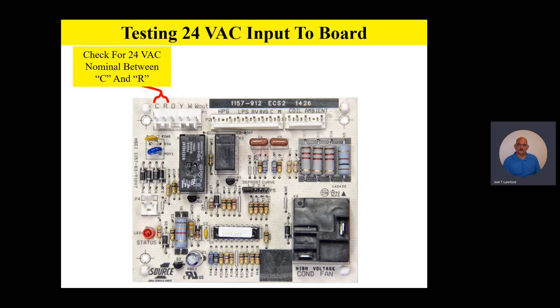So the first thing we like to do is always make sure we have 24-volt AC between the R and C terminals on the board itself. Now remember, team, the defrost control board has to have 24 volts to it all the time in order for it to function. On the thermostat itself, you're going to notice various inputs and outputs. You'll notice on the control board here, there's a Y and an O and a W and so on.